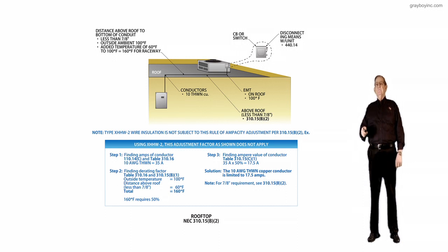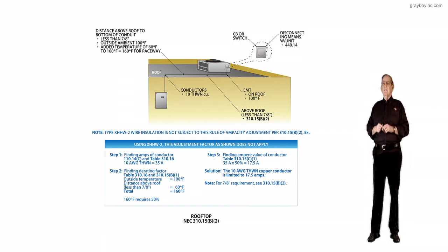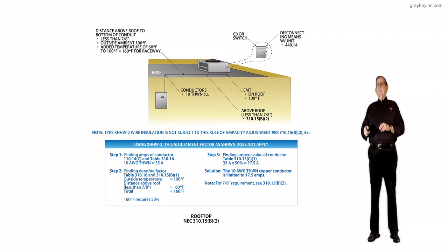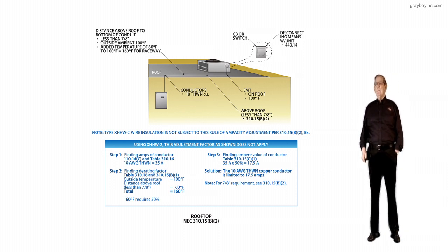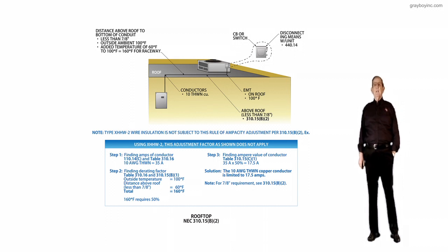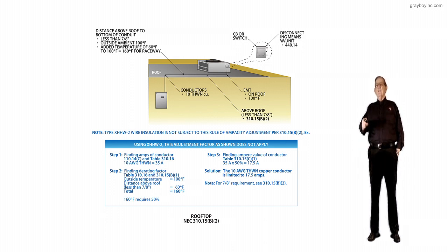Let's go to step 3. Using the table, we find that 50% of 35 is 17.5. The 10 AWG THWN copper conductor is limited to 17.5. So the 7 eighths requirements in accordance with 310.15B2, the new ampacity for that number 10 conductor is 17.5. That means it could only be put on a 20 amp circuit, and the current would be limited to 17.5 for your load. So can you afford that? You'd say no, I sure can't. So then just use your XHHW slash 2, and none of this applies.